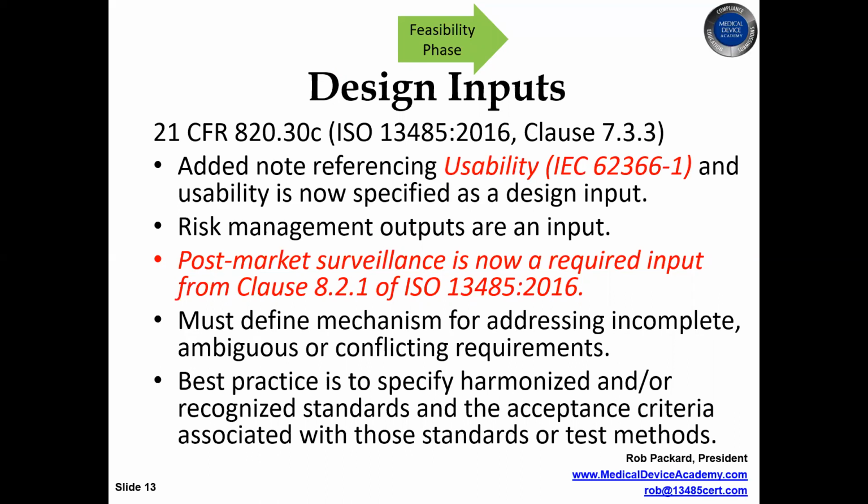This is also where you might start looking at usability as a design input for your project. And you also might be looking at interoperability with other accessory devices. So those are some things you have to consider in design inputs: usability, looking at use errors, and looking at interoperability with other accessory devices. And the FDA has actually published some guidance documents for both, but they have a usability standard that's referenced in ISO 13485:2016, and that's that standard.